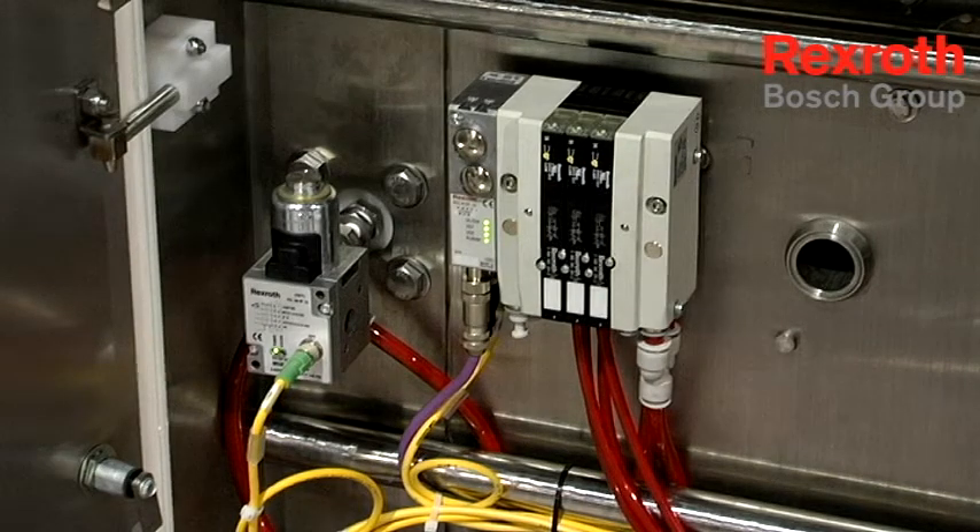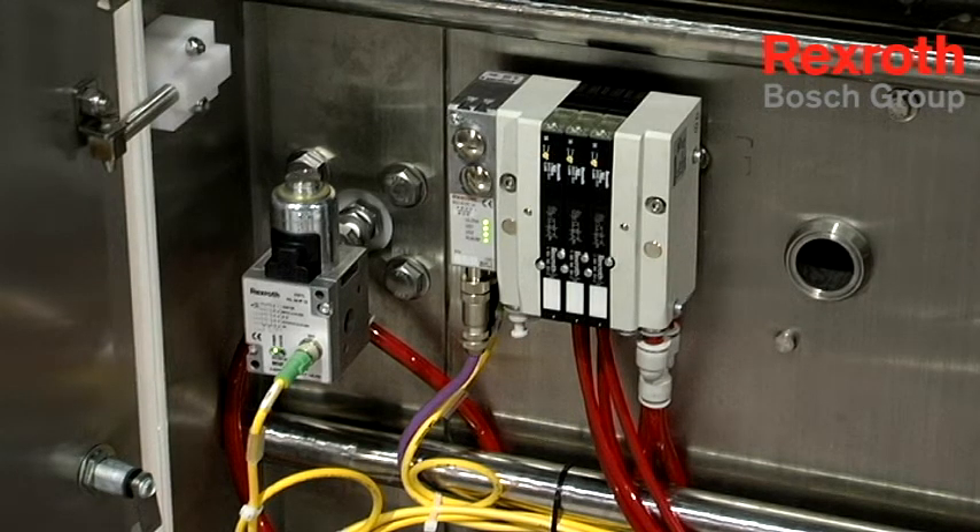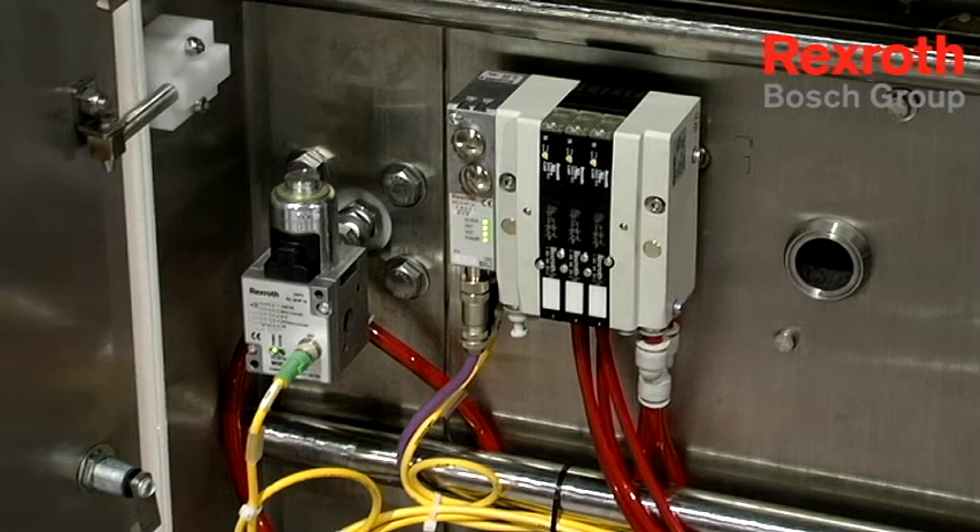The advantage of the HF03 is that it's a Profibus communication valve. By firing a series of up to 16 valves, we're doing it with one cable, eliminating cable runs on a machine. This allows for a cleaner approach to design, as well as removing components, which gives us a cost savings going back to our green philosophy.